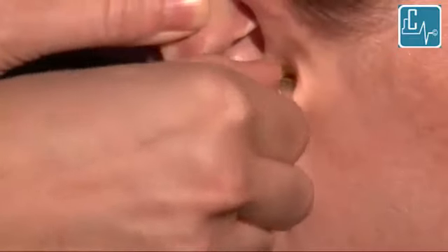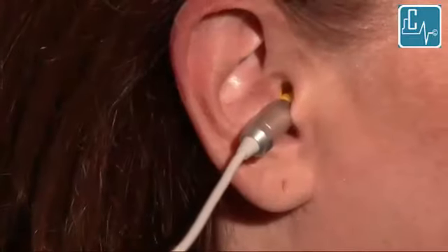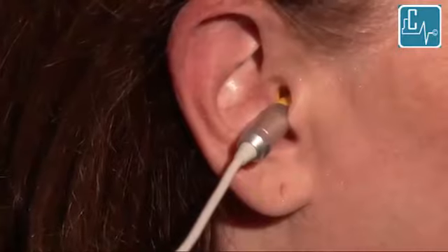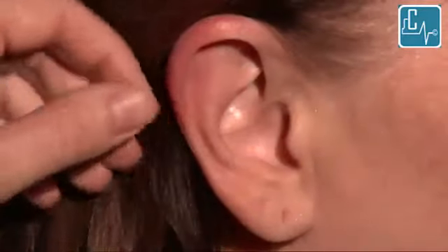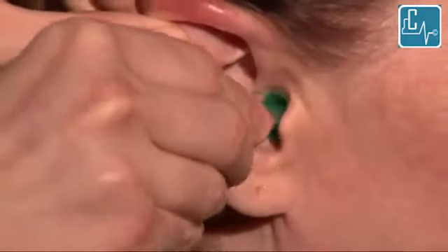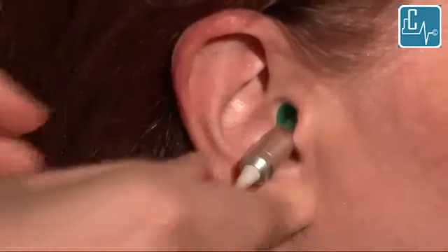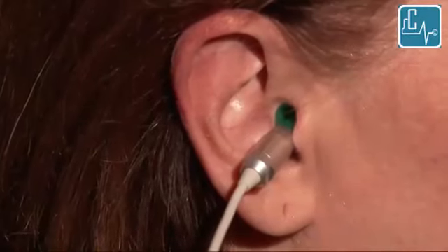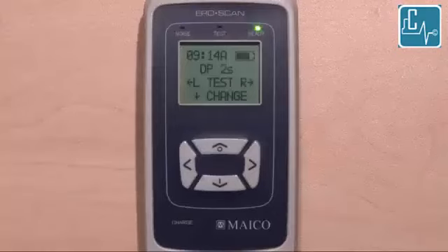The probe should not be handheld during the test, as this can introduce additional noise to the microphone inside the probe during the test procedure. If the probe does not stay in place, try a different size ear tip and reinsert the probe.